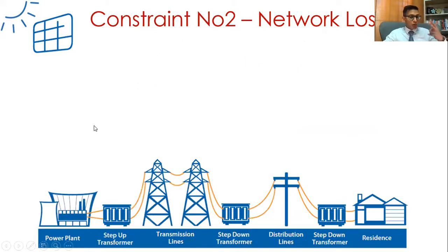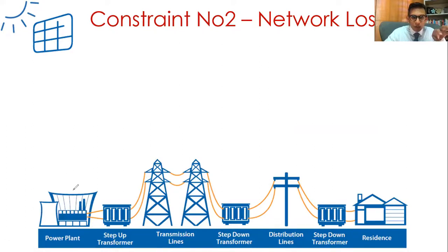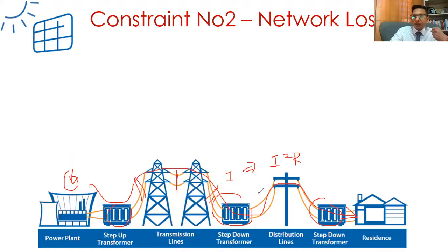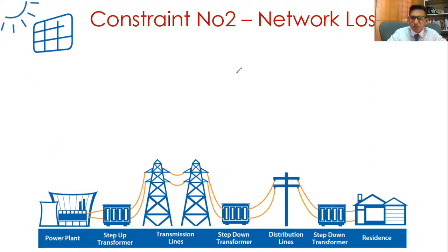Let's talk about network losses. We have the power plant on one side and loads on the other. When we have power flow, we have current flowing, and when current flows, we have what we call I-squared R losses - losses in transformers and in the power lines. It is inherent to power systems. It's a key metric for power utilities to keep losses within a low range, because it is wasted energy - energy that could have been used to supply people. You can decrease network losses by using bigger conductors, better quality transformers, and so on.